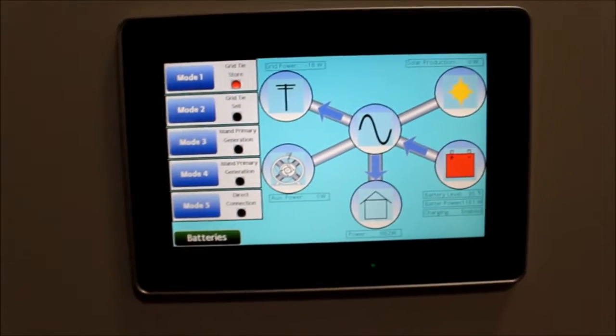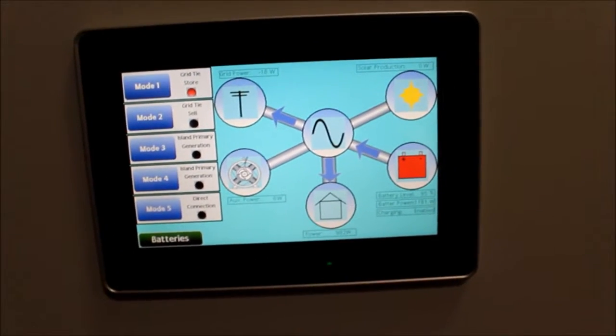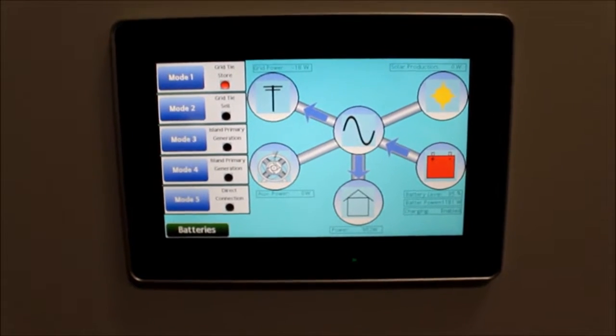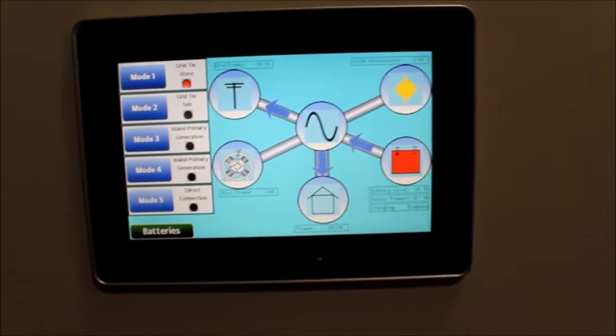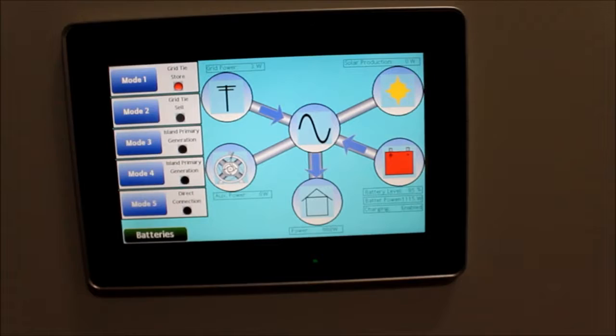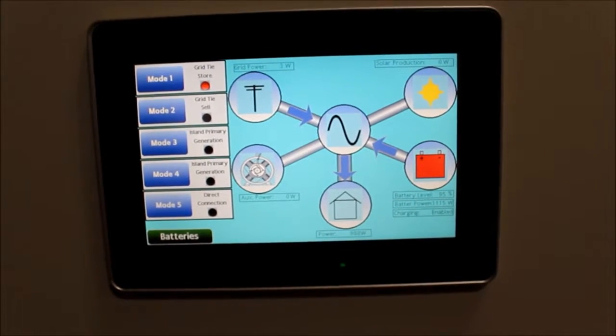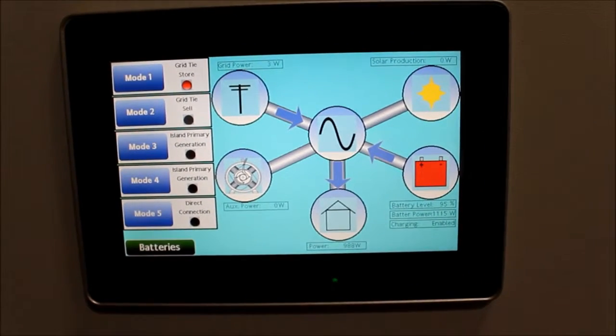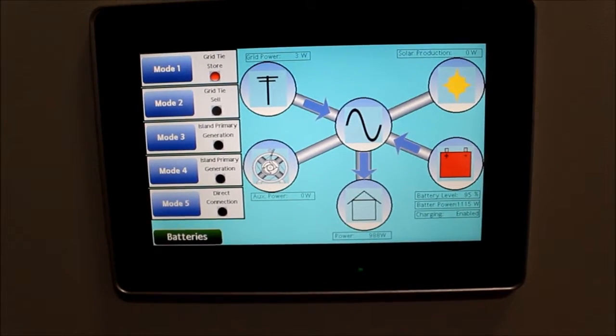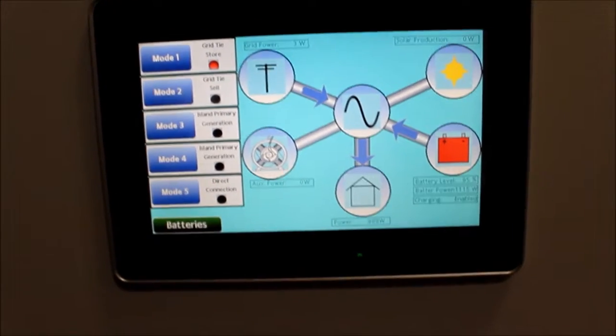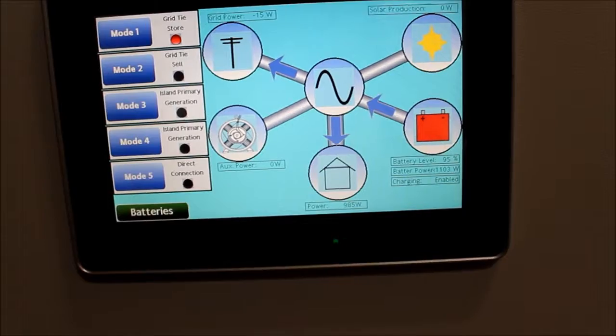Okay. And at this point the battery top-off procedure is complete, so it's actually showing 18 watts flowing back to the grid, now 3 watts flowing to the energy switch. That is essentially a zero value. There is no power flowing into or out of the system, and right now the system is able to serve the load solely from batteries.